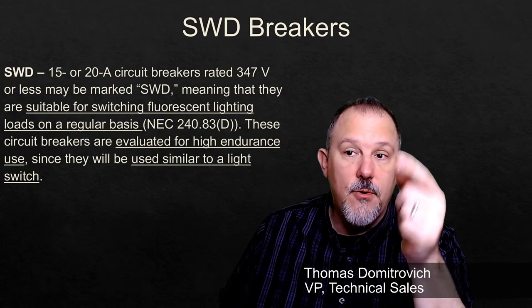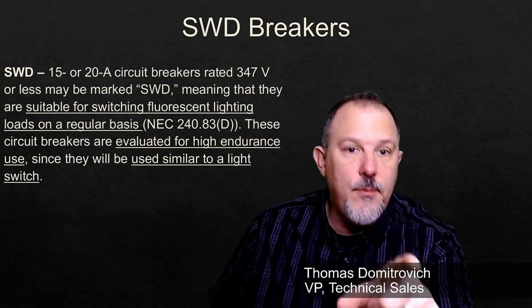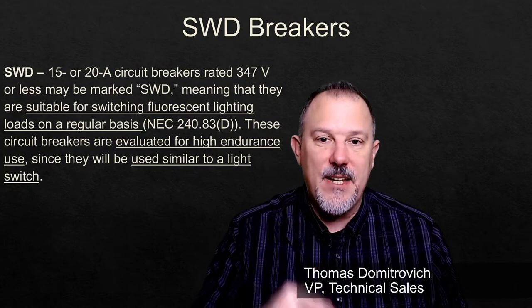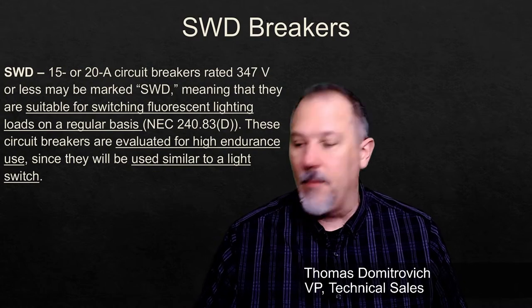If I had my buddy Lou Grayhor on here, he could probably tell you. Suitable for switching. So SWD, circuit breakers rated 347 volts or less may be marked 15 or 20 amps SWD, which means they are suitable for switching fluorescent lighting loads on a regular basis.